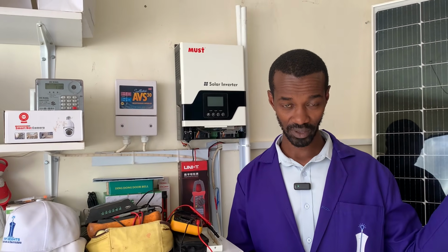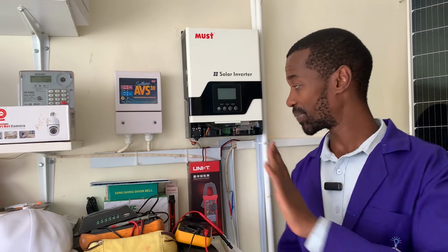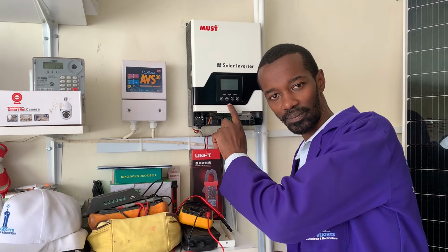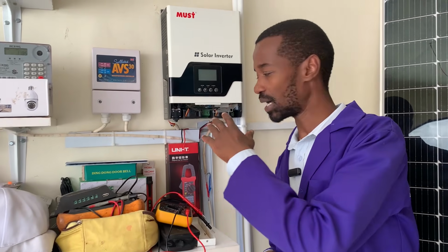If you start with the PV, it means that the high voltage from the panels might damage the inverter as well, because that will be floating voltage. It needs to be directed somewhere, which is the battery. The only method that we need to do here is to ensure that we start with the battery.